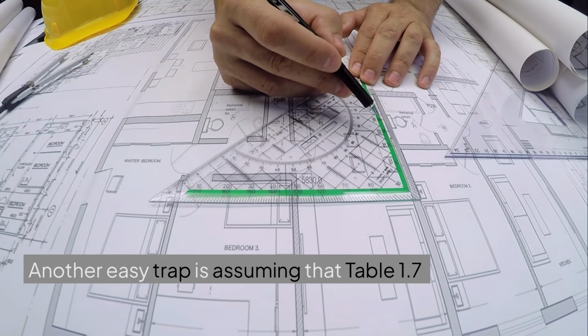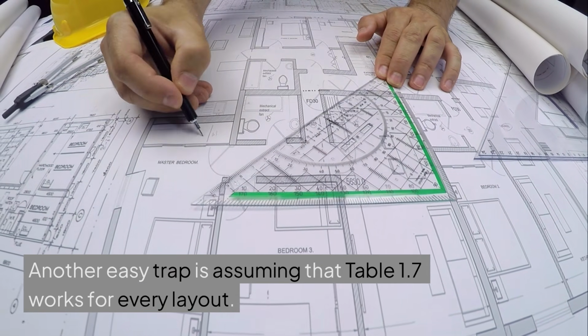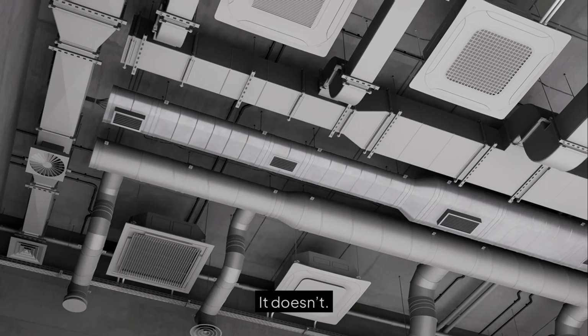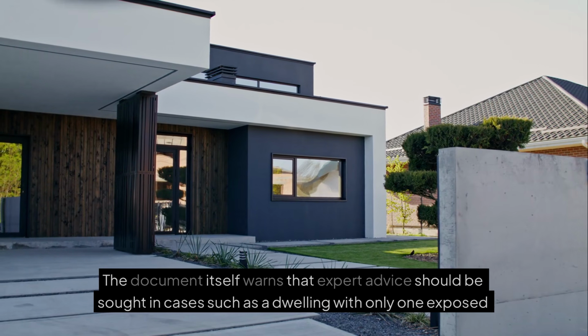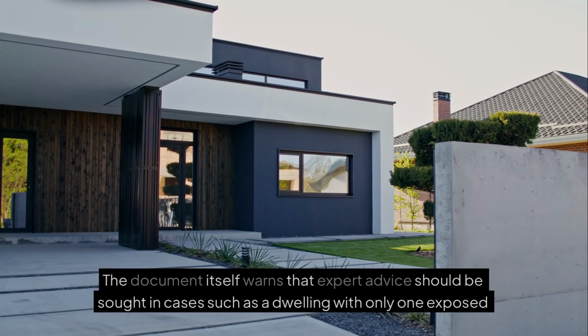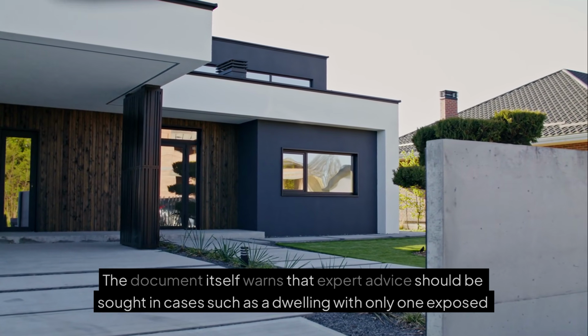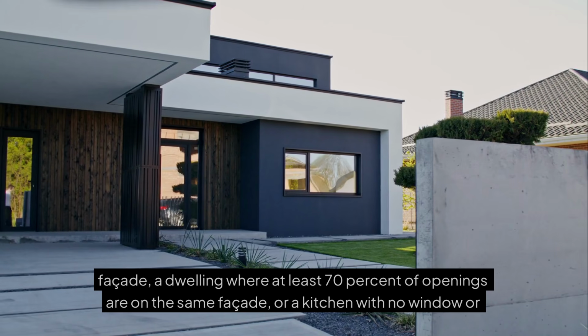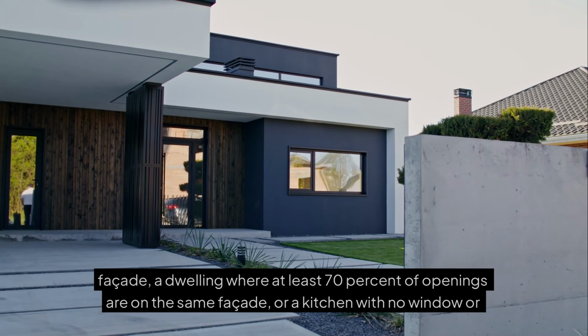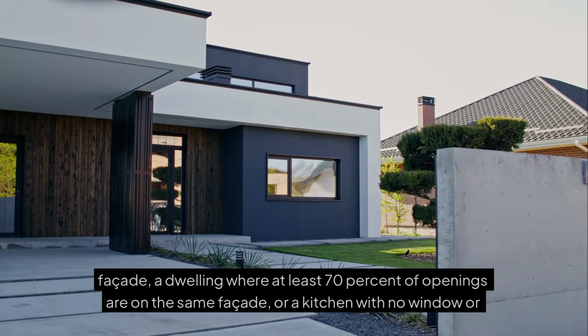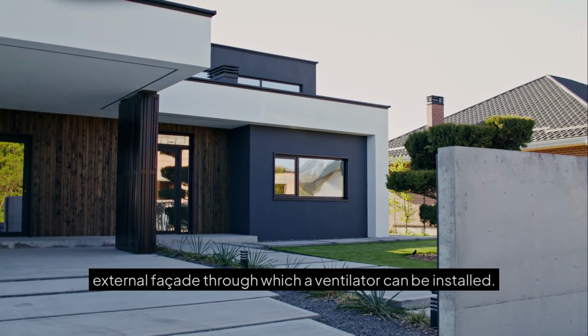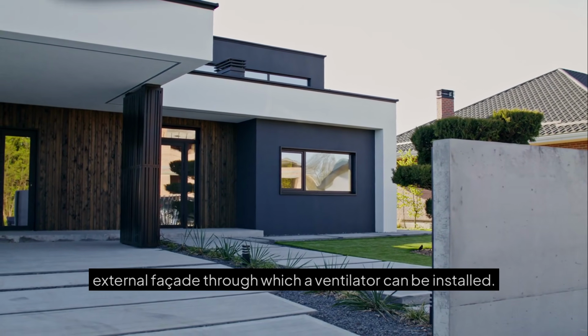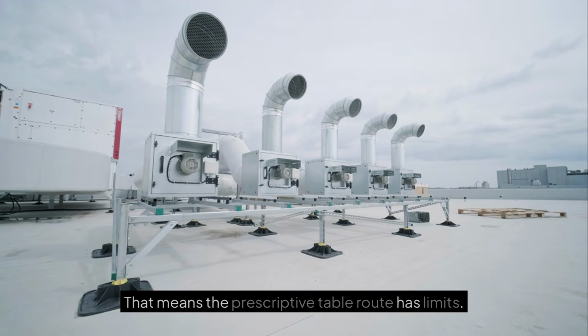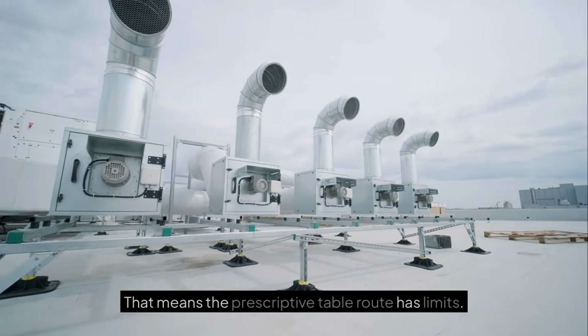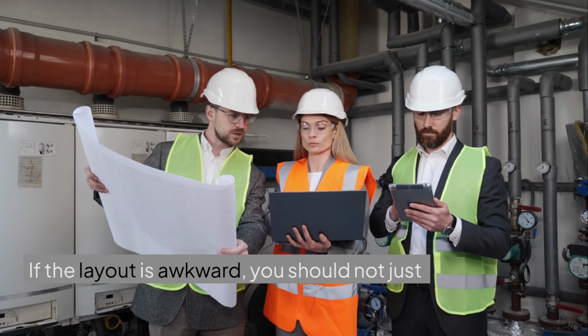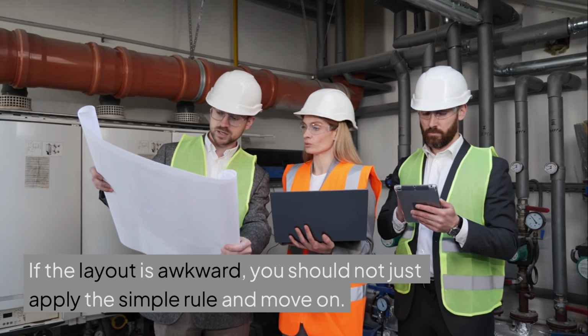Another easy trap is assuming that Table 1.7 works for every layout. It doesn't. The document itself warns that expert advice should be sought in cases such as a dwelling with only one exposed facade, a dwelling where at least 70% of openings are on the same facade, or a kitchen with no window or external facade through which a ventilator can be installed. That means the prescriptive table route has limits. If the layout is awkward, you should not just apply the simple rule and move on.